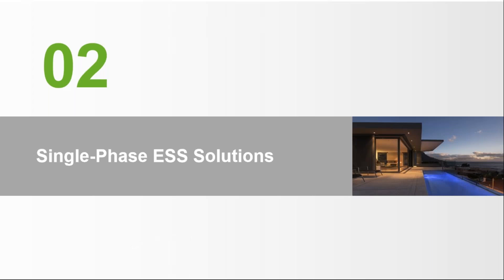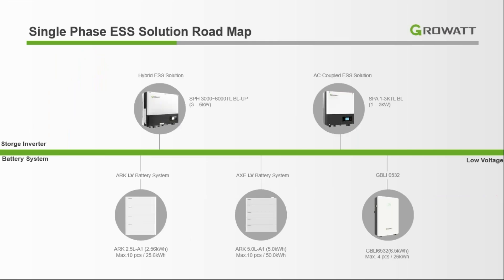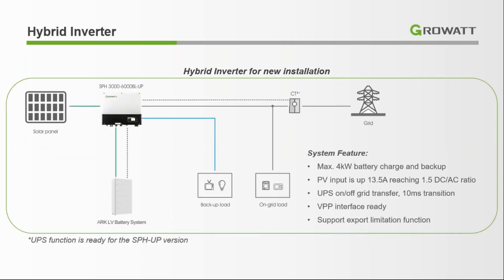Now I'm going to discuss the single phase ESS solution. Here is the roadmap — on the left side is our SPH model and on the right side is the SPA model. The SPH model supports low voltage batteries. We can connect up to 4 kWh of battery bank. The PV input is up to 13.5A reaching a 1.5 DC-to-AC ratio. When the grid cuts off, it takes just 10 milliseconds to switch to UPS mode. It can act as a UPS — we can connect critical loads as well as high AC loads to this inverter.